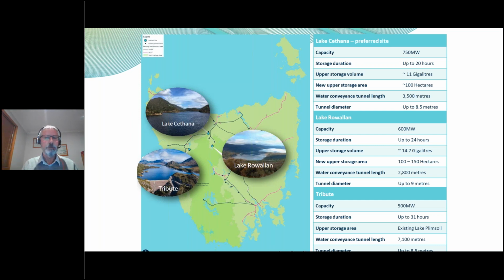Matt also touched on high heads. One of our criteria for site selection set a minimum head of 300 metres, but from our experience that was probably too low - we'd look to 500 to 600 metres of head to maximise energy storage without the need for very large upper storages. The other key aspect, short connection distances, matters because these projects tend to be underground developments with underground tunnel connections, which is a very costly part of developing a pumped hydro project. So the shorter the connection distances, the more cost effective they will be.